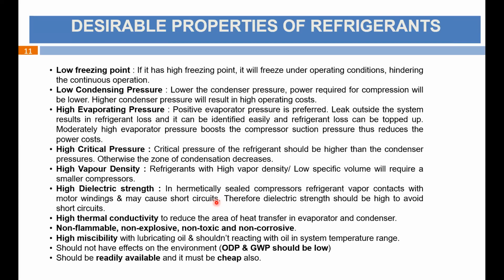As you know, in that case the compression ratio will be lower, and so there will be lower condensing pressure. As you know, higher condenser pressure is equivalent to higher operating cost for any air conditioning or refrigeration system. So the refrigerant should have low condensing pressure. Similarly, it should have high evaporating pressure.